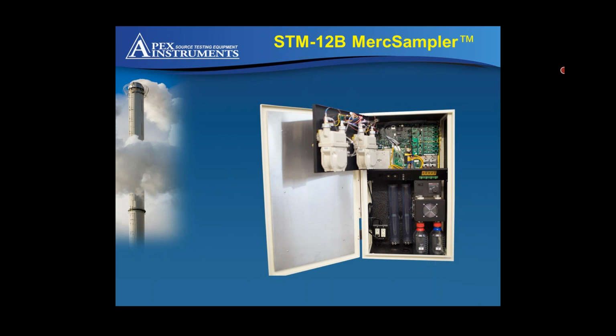Right. Stuff like the purifil, if you don't change it or you don't empty your condensate bottles, you can back water up into the console, and that's kind of a serious thing that can happen. So you're changing the carbon in the purifil at each trap change? Not necessarily. Usually there's multiple sections in there. Again, it's going to depend on what your stack is, how much moisture and things like that. A lot of times we'll see them change the silica, which is just the top half of the cartridge, more often than the carbon. The carbon will go for a month.